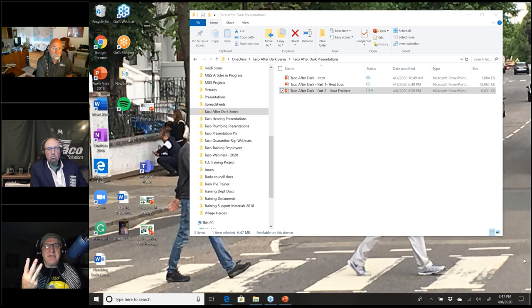Well, what you can do then is have the boiler set the benchmark for the highest water temperature you're going to need in the system. And then you can do a secondary reset with the two lower water temperatures using, let's say, a Taco i-valve or something like that. Now you're resetting off of the reset. So it may sound like overkill, but think about it.